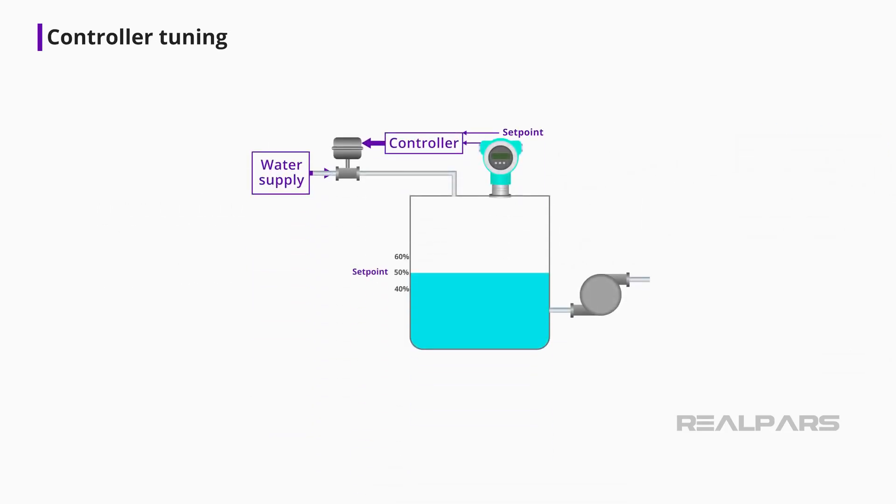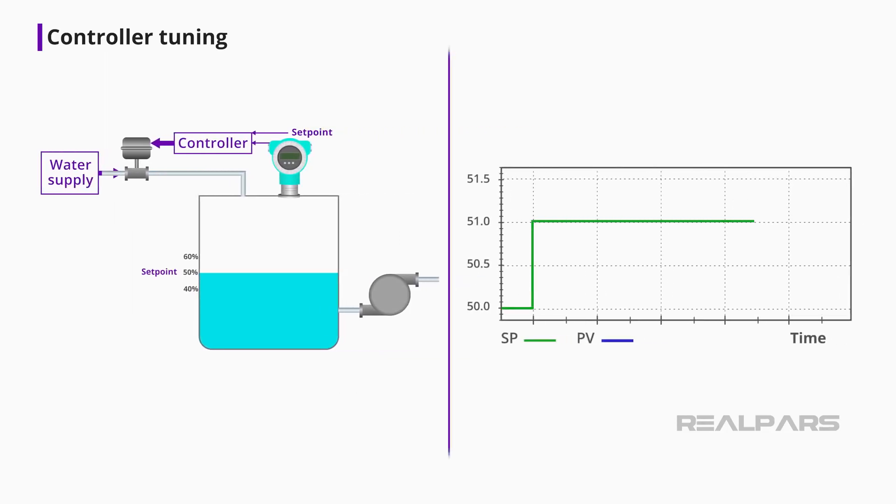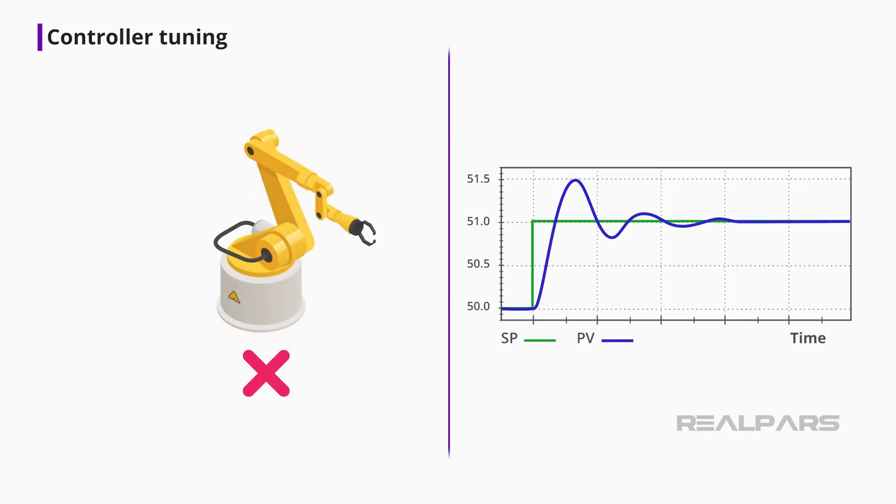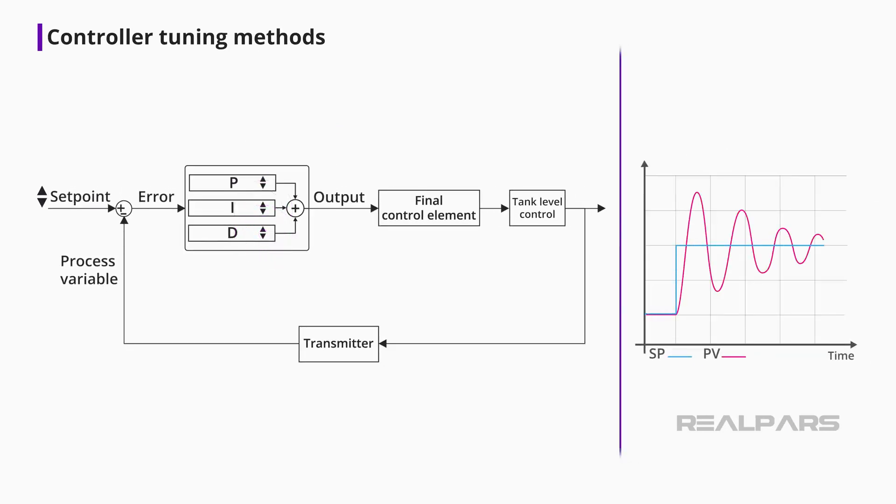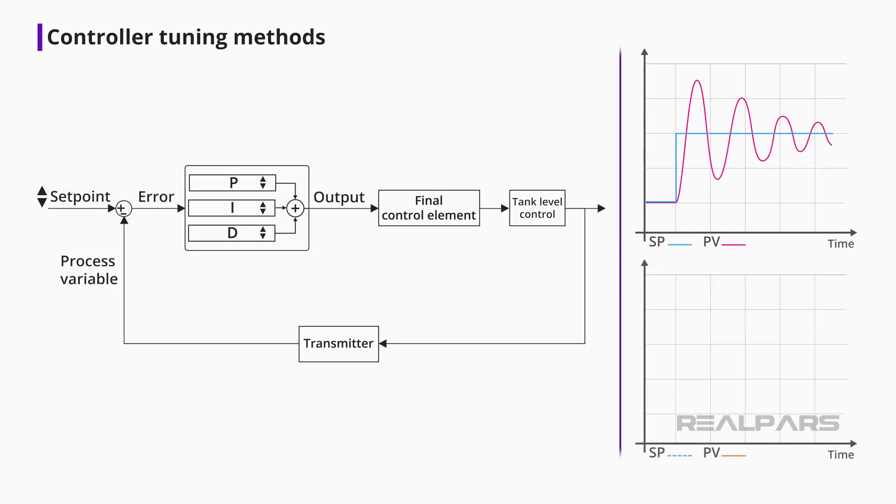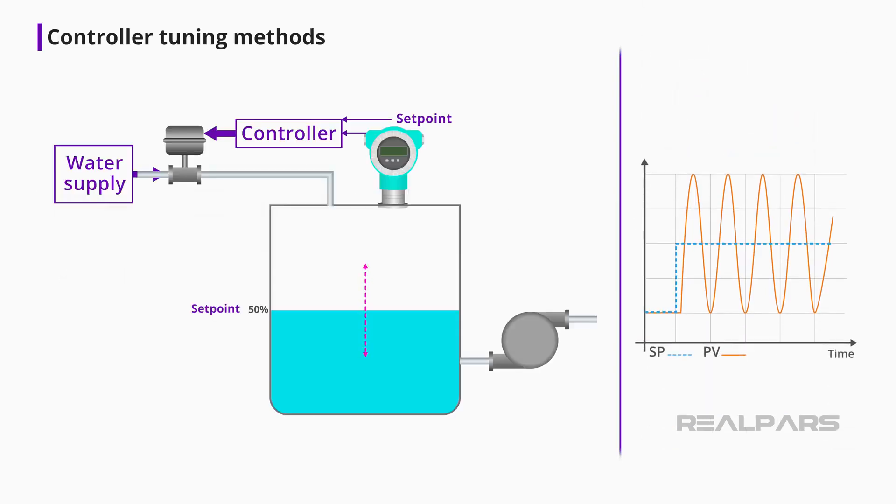For example, after the controller has been tuned, a setpoint bump of 1% in a tank-level control produces a quarter-wave damped response. This type of response may be suitable in a tank-level process, but could be disastrous in a motion control process. There are many different manual methods for tuning a controller that involves observing the process response after inflicting controller setpoint changes. One method involves increasing the amount of setpoint change and repeating the procedure until the process enters a state of steady-state oscillation. This method of tuning produces adequate results, but is often impractical in many applications. For example, how practical is it to force the fluid level in a large tank to reach a steady-state oscillation?